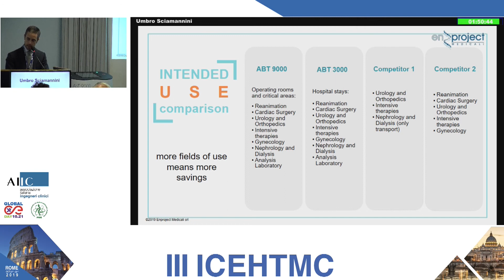The second area of our comparison is about the action and treatment of waste. ABT does a degradation and retrovirus inhibition of biological liquids, as we say. It also disinfects antiblastic tracers and exhausted chemical reagents, and neutralizes dialysis ultrafiltrate, while the other two competitors do just an aspiration of biological liquids, and the decontamination is made by adding other products at the discretion of the operator. Of course, it would be better if the device made decontamination less at the discretion of the operator as much as possible. So, we can say attention must be paid to the treatment of the waste and not only to their aspiration.